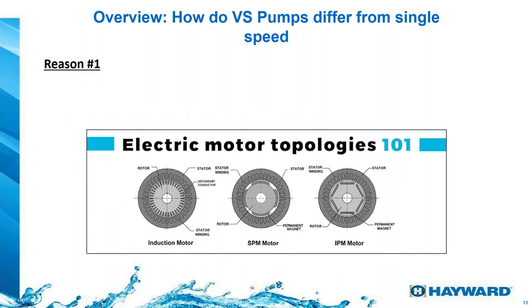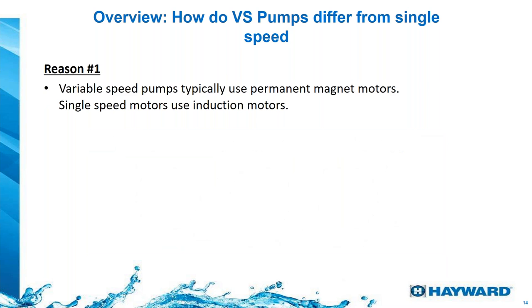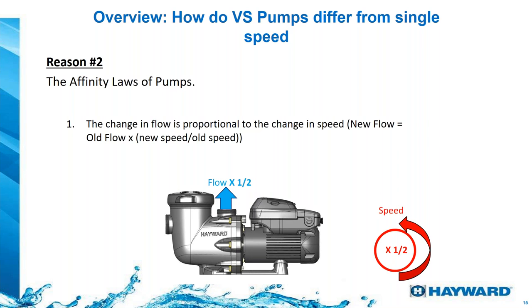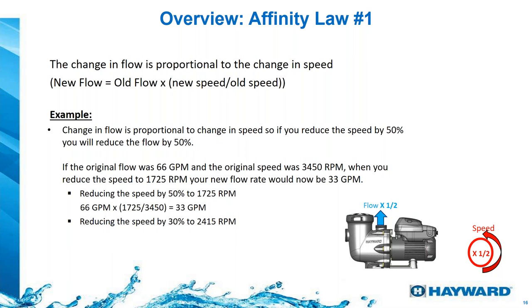How does that benefit us? First, variable speed pumps use a motor with a permanent magnet — not an induction motor — which is a big saving right there. By reducing the speed by half, we obtain half the flow. For example, if we're moving 66 gallons per minute, reducing speed by half gives us 33 gallons per minute. If we reduce speed by 30%, instead of 66 GPM, we'll obtain 46.2 GPM. These flow examples go together with the change in head — the hydraulic resistance.